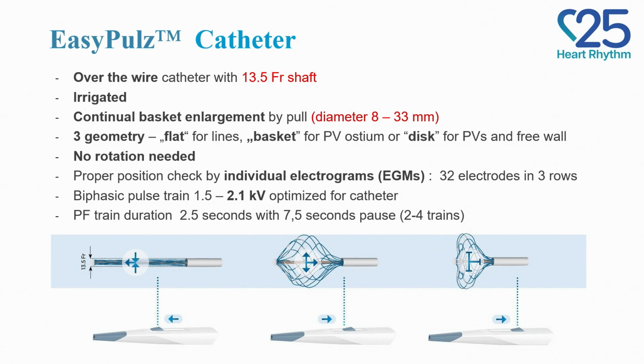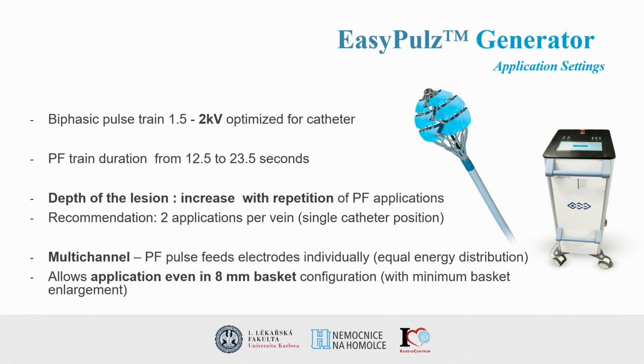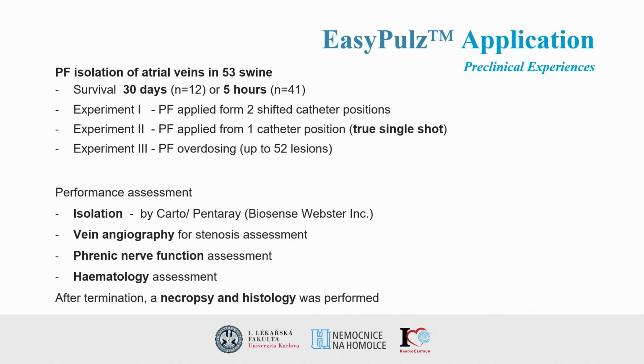So the biphasic pulse is designed to get more than 2 kilovolts, optimized for the catheter, and the pulsing is going from all these elements. So the PF train delivery is in total 10 seconds, because after 2.5 seconds of application there is some pausing, because actually the engineers really want to avoid overheating. So this is again the same. Because of shorter time, we can skip this.